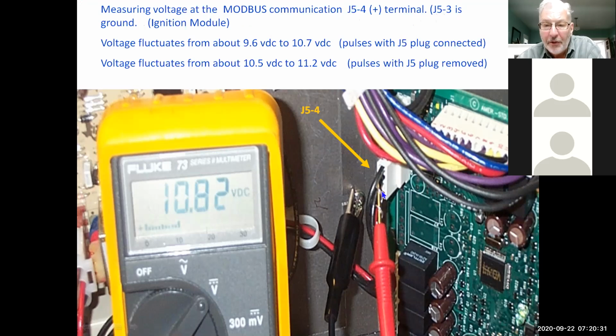So J5 goes to your ignition module, and the 2 black wires are communication. So what you should see is about 10 volts, 10.2, what they have up here, 9.6 to 10.7 volts DC. It's going to move around a little bit, but on the Modbus, what you're going to see is a 4-wire connector, and there's going to be 2 black wires, a blue and a red. The 2 black wires are your communication wires, and the blue is your common, the red is your 24-volt hot. So when we plug these boards in, we use the 24-volt hot and common to power the board, and then we measure our communication voltage on the Modbus, which are the 2 black wires. If you pull or disconnect the wires, you might see 10.5 to 11 or 11.2 volts DC. So there's some fluctuation there when you do unplug them.